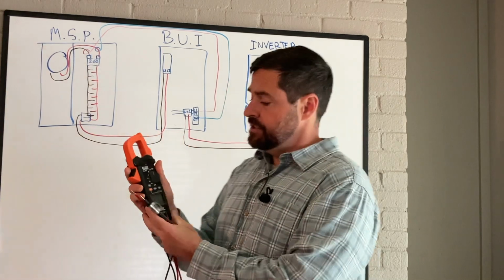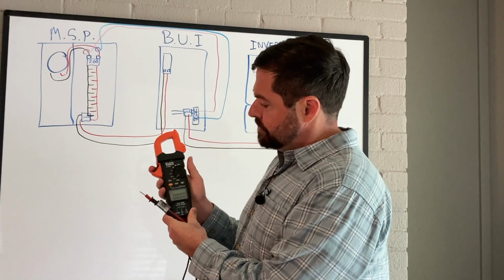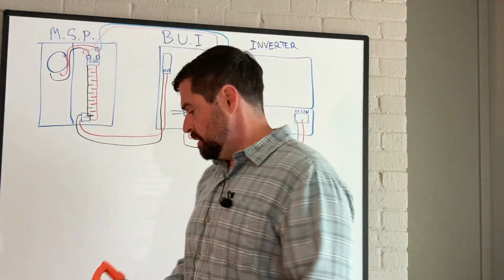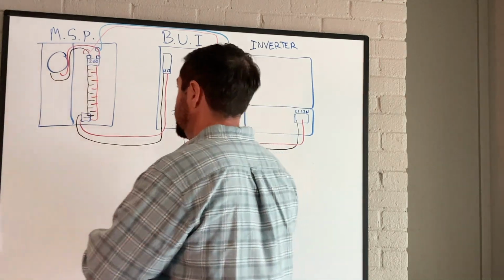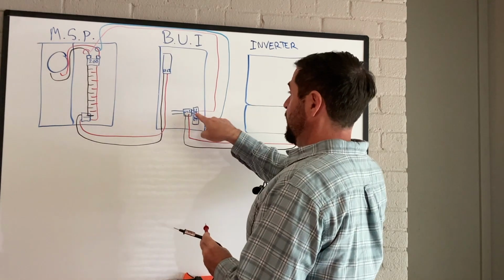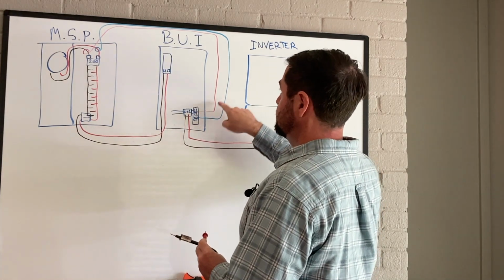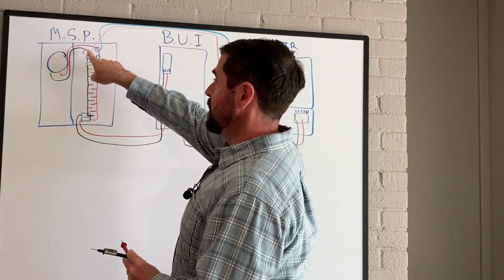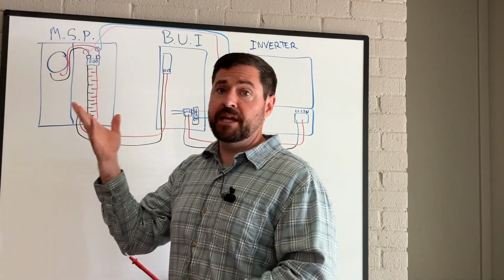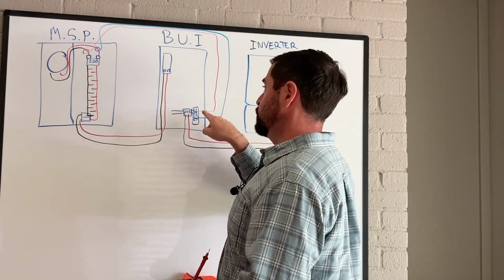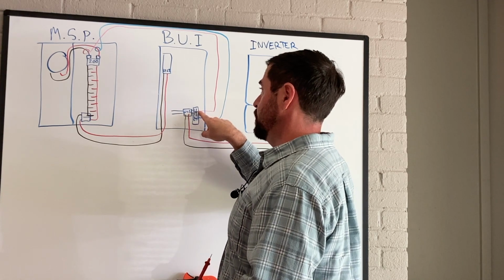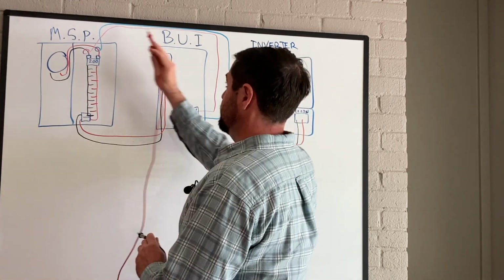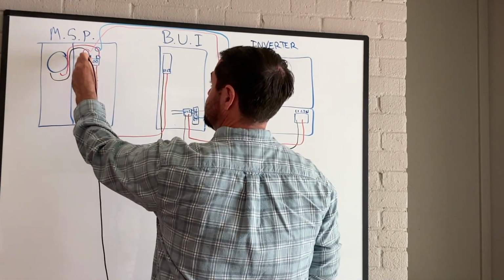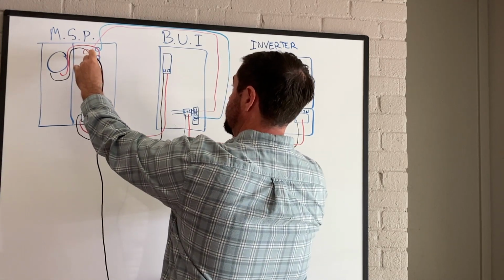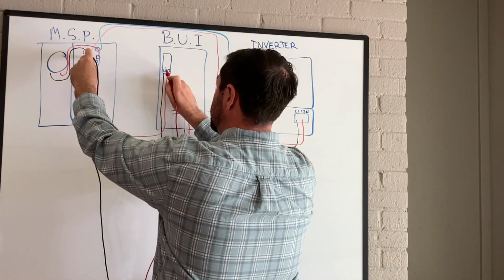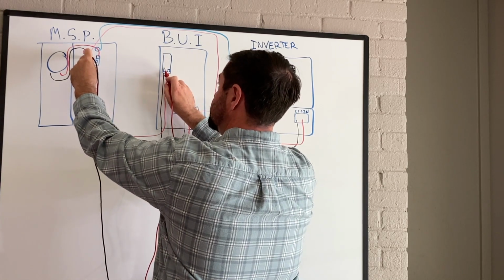So first, what you do is you turn the voltmeter to volts, alternating current. From there, you take one probe, you find where the L1 CT coming out of the energy meter is. You trace that and you figure out, right, it doesn't matter if it's black or red or pink. It just matters which wire is the CT terminated into the L1 port of the energy meter. In this case, it's the pink CT. So we're going to check that lug, and then we're going to put our other end of our voltmeter on the L1 lug in the backup interface. We want to see 0 volts.